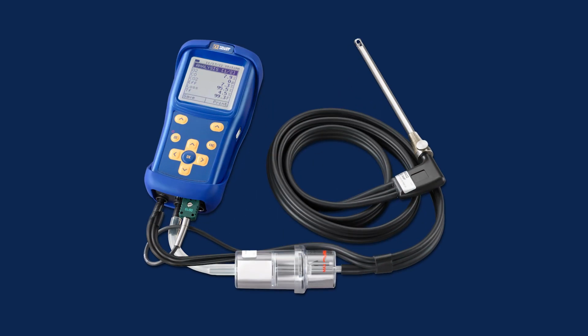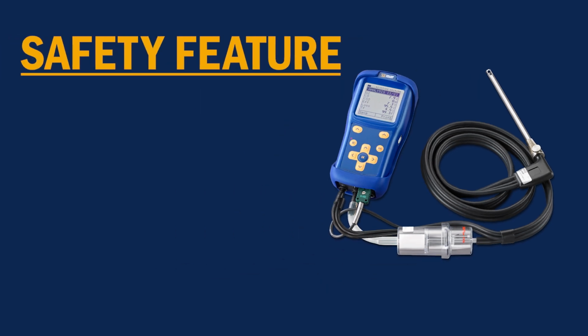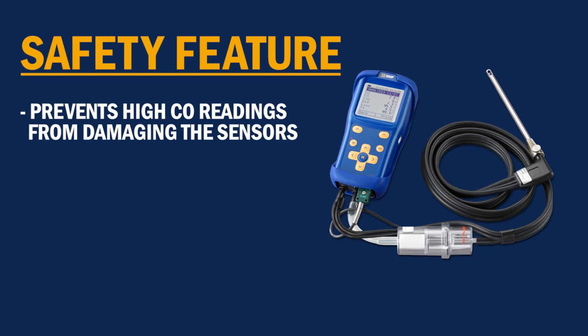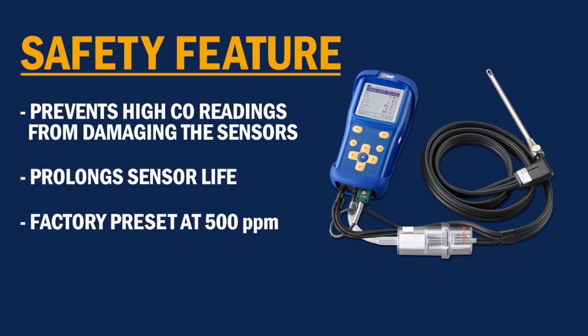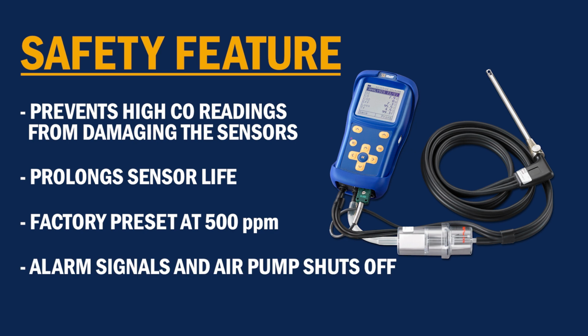The CA502 Combustion Analyzer is made with a safety feature to prevent high CO readings from damaging the sensors, and it prolongs the sensor's life. At 500 parts per million, a factory preset will trigger an alarm and the air pump will automatically shut off.